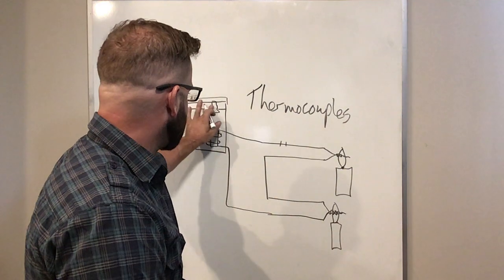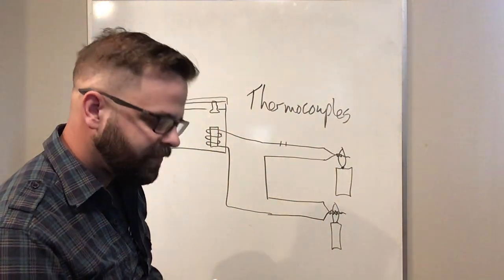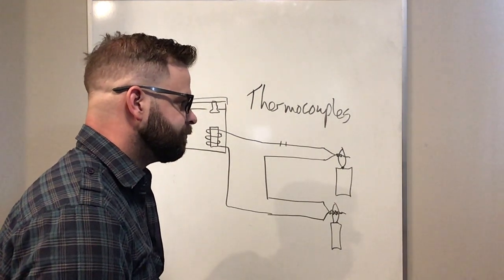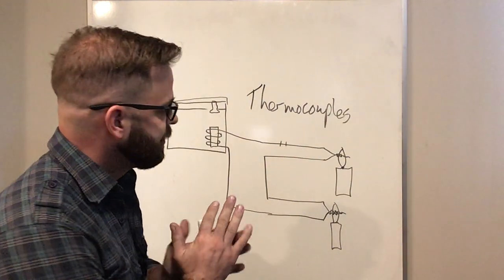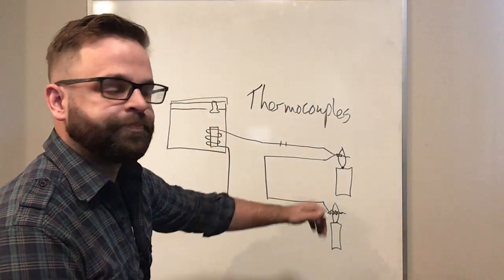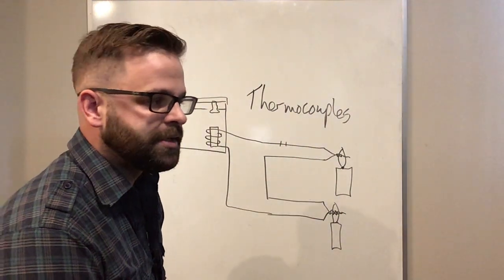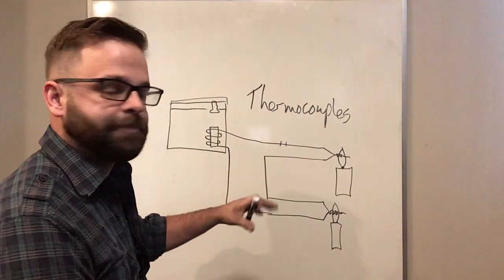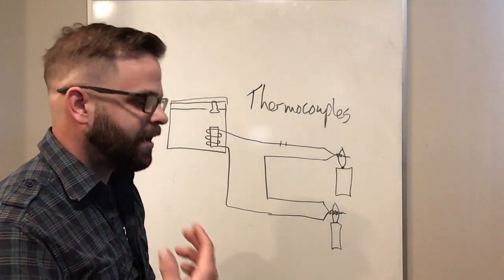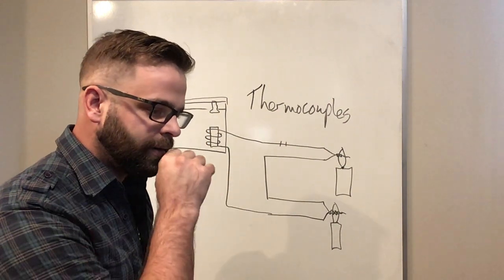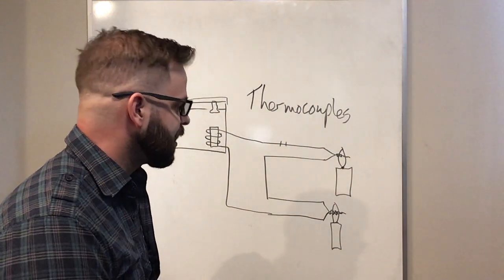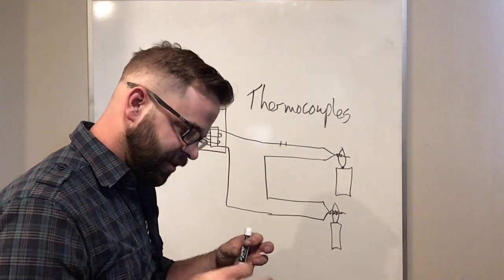And restricting the flow of gas through that gas valve. These are used a lot like a safety feature in gas appliances. So if there's no flame present, I won't be able to start up my gas appliance. Or let's say I have a flame and my gas valve is open and everything's working properly, and then possibly there's an issue, maybe I have a downdraft, or I start getting a lot of soot inside or being produced, or that thermocouple or thermopile gets covered in soot.